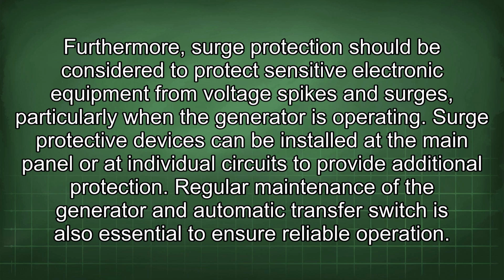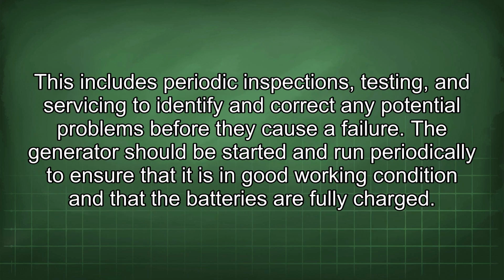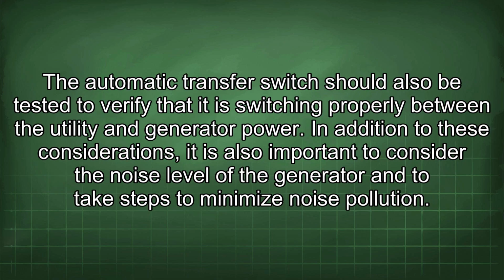Regular maintenance of the generator and automatic transfer switch is also essential to ensure reliable operation. This includes periodic inspections, testing, and servicing to identify and correct any potential problems before they cause a failure. The generator should be started and run periodically to ensure that it is in good working condition and that the batteries are fully charged. The automatic transfer switch should also be tested to verify that it is switching properly between the utility and generator power.